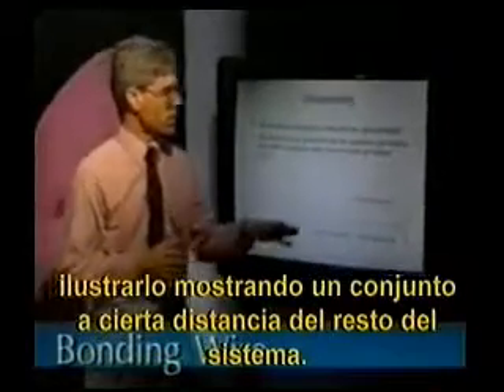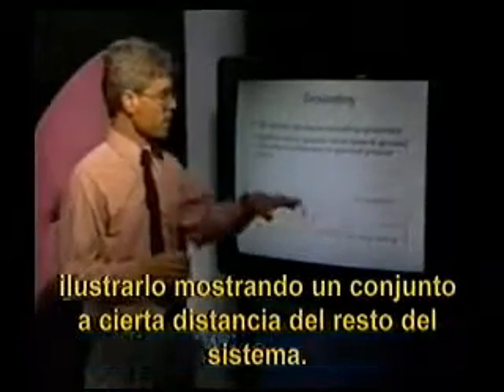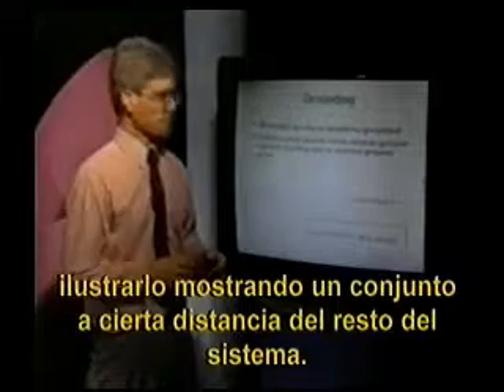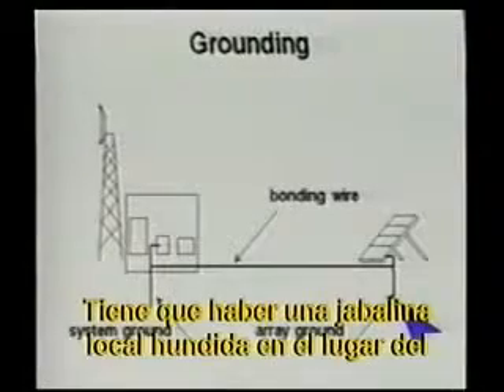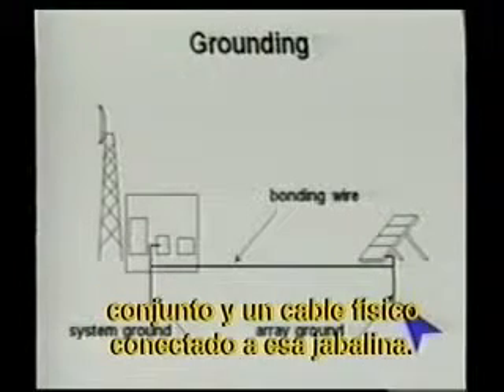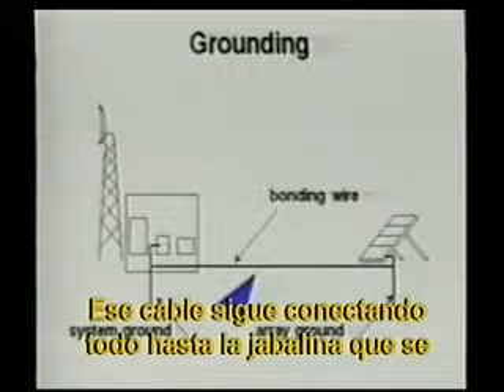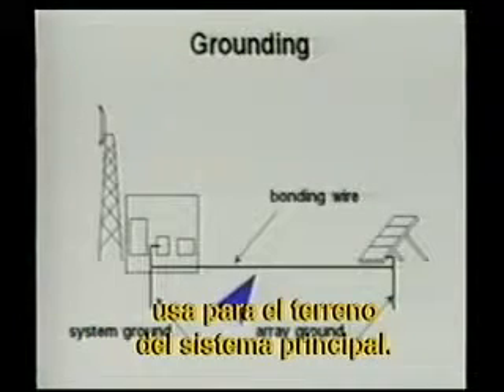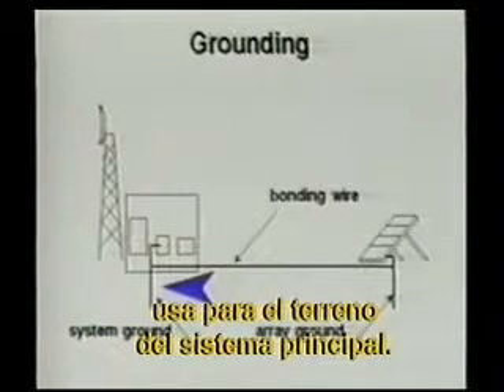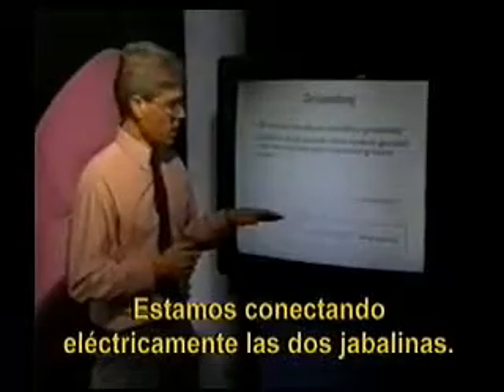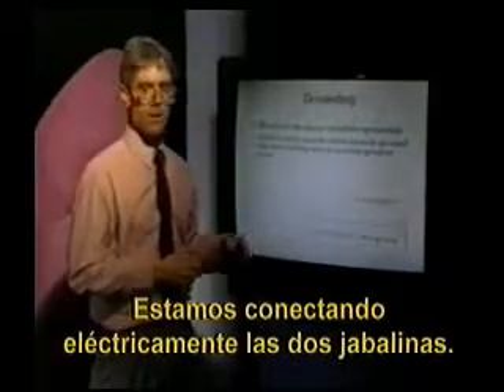We can illustrate it by showing an array some distance from the rest of our system. We should have a local rod sunk at the array, or at the arrays if we have multiple ones, and then a physical wire connected to that ground rod that is connected all the way in to the rod that's used for our main system ground. We're electrically connecting the two rods together.